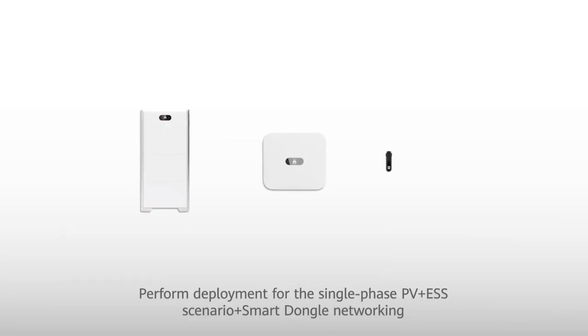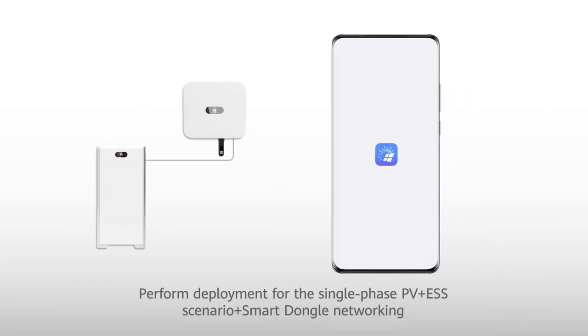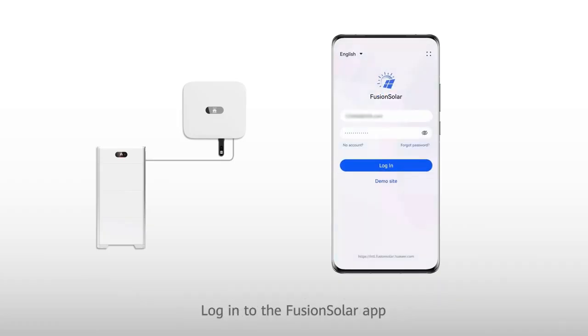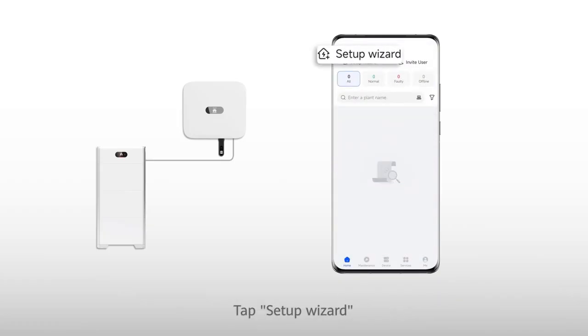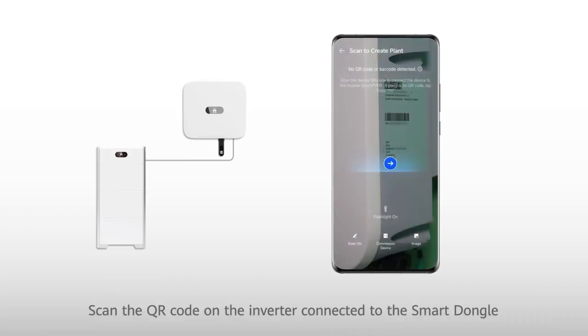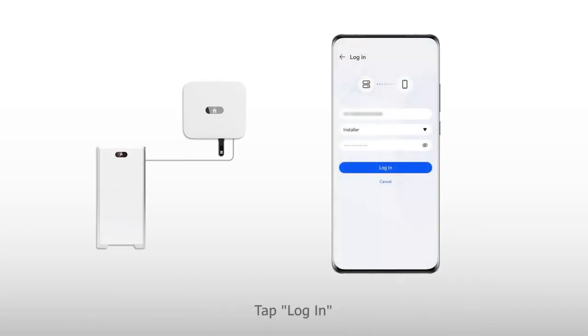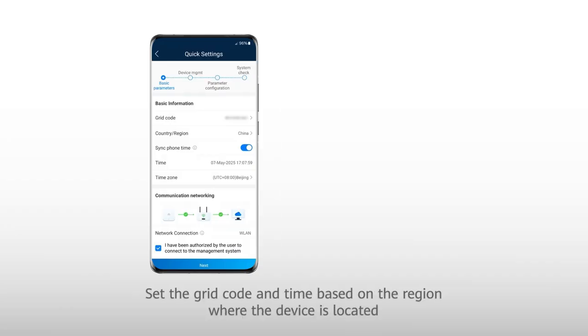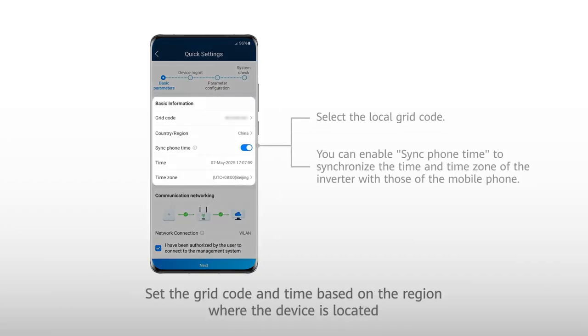Perform deployment for the single-phase PV plus ESS scenario plus Smart Dongle networking. Log in to the FusionSolar app. Tap Setup Wizard. Scan the QR code on the inverter connected to the Smart Dongle. Tap Log in. Set the grid code and time based on the region where the device is located.